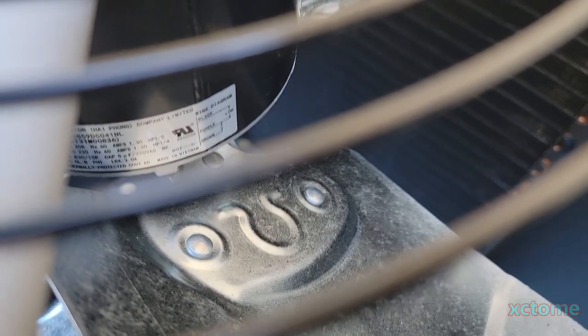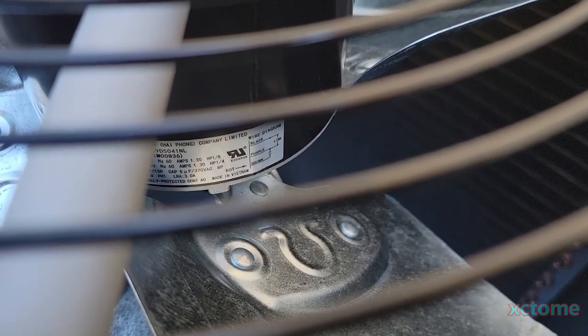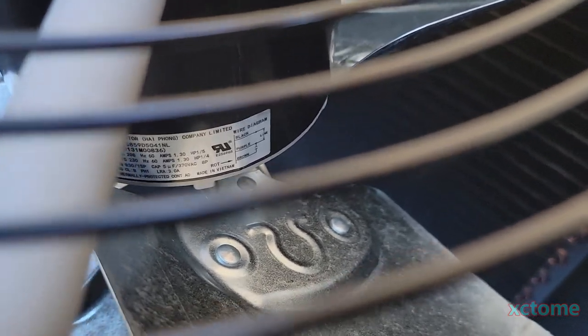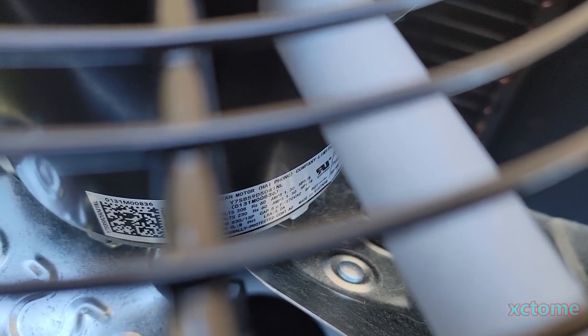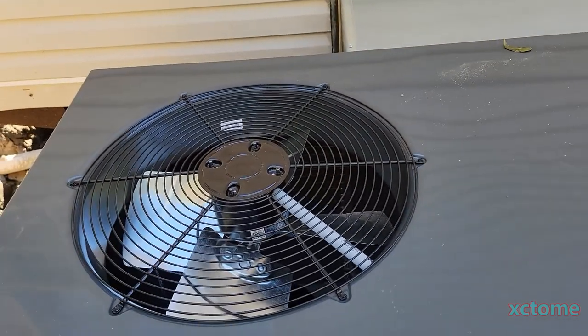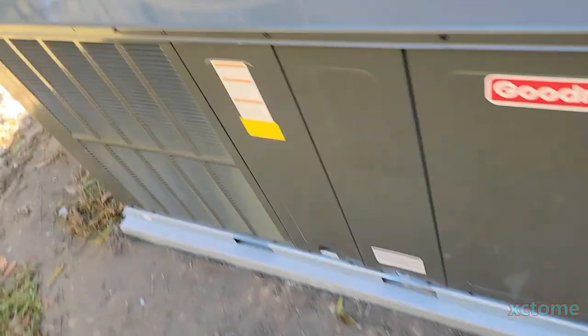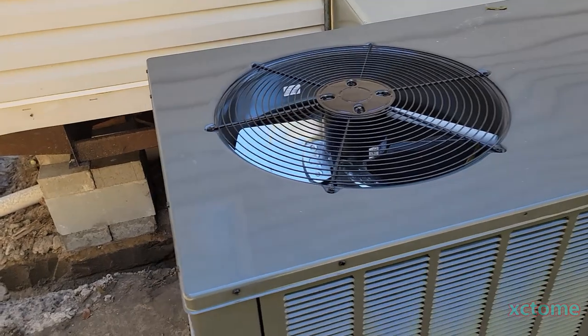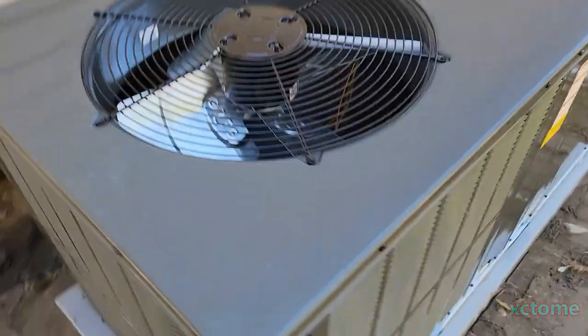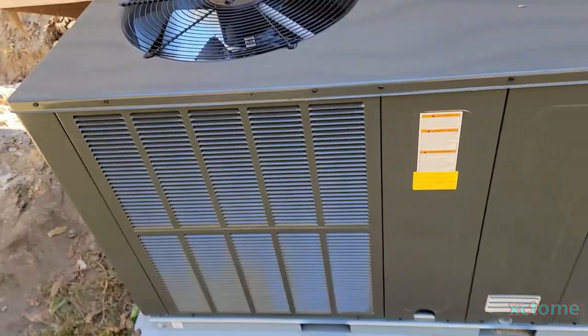It's wired up for 230 volts, showing quarter horsepower. Interestingly, it's not made in China anymore — maybe they've gotten better in quality. It's a Broad Ocean Motor Company Limited, 830 RPM. My old unit was 1,122 RPM. I don't know what blower it has — I imagine a Genteq blower because this is an ECM multi-speed blower. It's not a true variable like my unit or the split system at the other place. I think it's a multi-step ECM motor or fixed speed; I haven't opened the control panel and I don't have my tools with me right now.